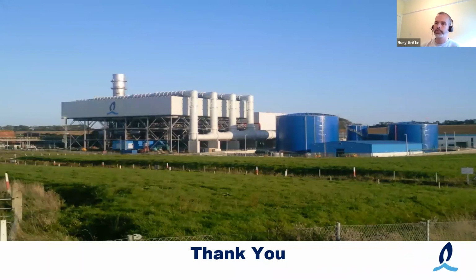So as the unit's spinning up, the generator itself is quite large. It's a 535 MVA generator. On an electrical note, if you start any motor, you get a very high inrush current at the start because there's torque to overcome once you get the machine turning. So when Whitegate is running up to synchronize, you can suck in up to 18 megawatts of house load while the line commutated inverter is bringing that generator up to synchronous speed, up to 3000 RPM. So we would need a supply external to the station that's at least 18 to 20 megawatts to start up Whitegate.